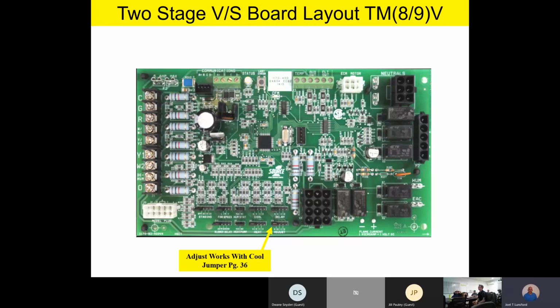But what that is, that adjust jumper works with the cool jumper. So let me say that again. The cool and the adjust jumper work together to set up your cooling airflow. Please note this. When you take a look at your install information, it used to be housed on page 36. It might still be page 36. You're going to find that the cool and the adjust jumper work together to set up your cooling airflow. Please make a mental note of this. The cool and the adjust jumper is your Y2 airflow.